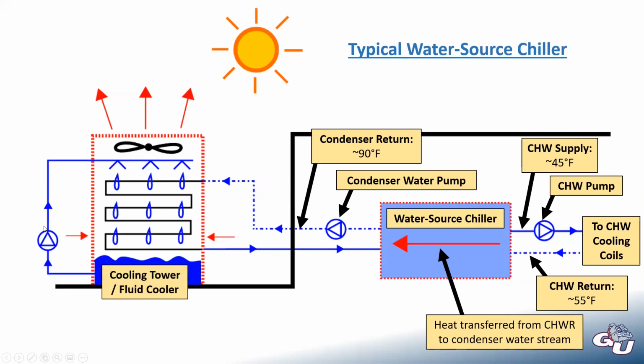You can see we have a third pump over here and a little basin filled with water inside this tower. And this pump is taking water from the basin, pumping it up through some spray nozzles, and basically misting water over this coil that's in here. So we're sending our water in here, and you can see this water has multiple passes through the cooling tower as we are spraying it with this basin water.